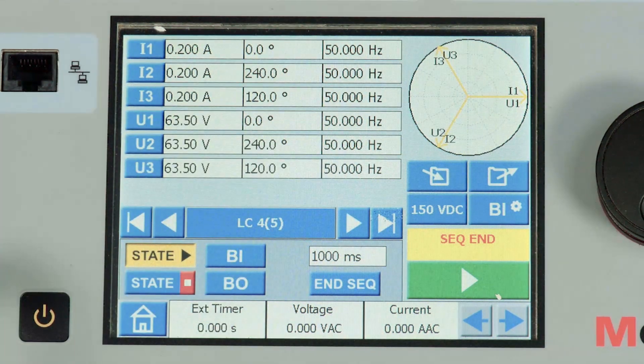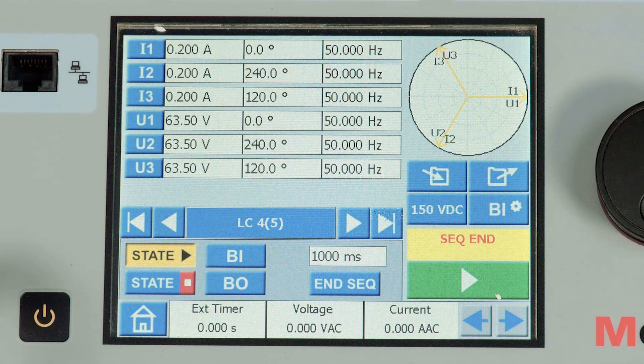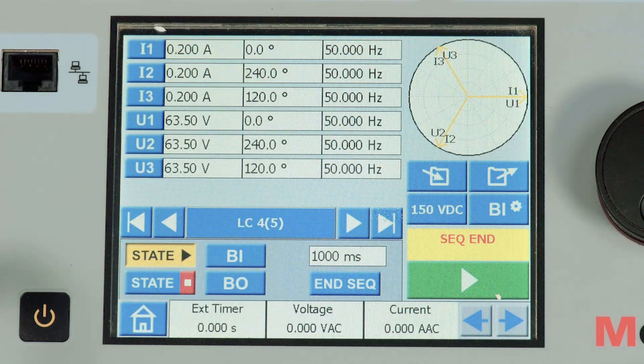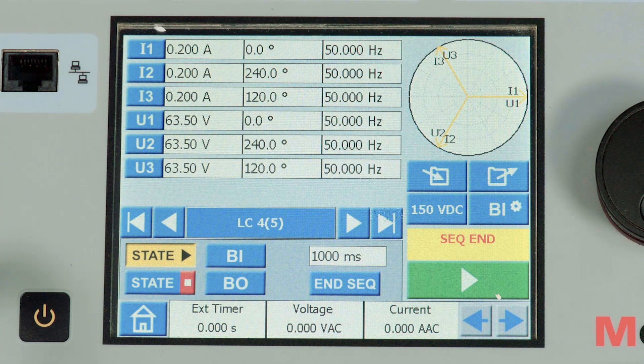State 4 is the breaker closing identification by the relay. A small amount of current and voltage is applied for successful detection of breaker closure by the relay.